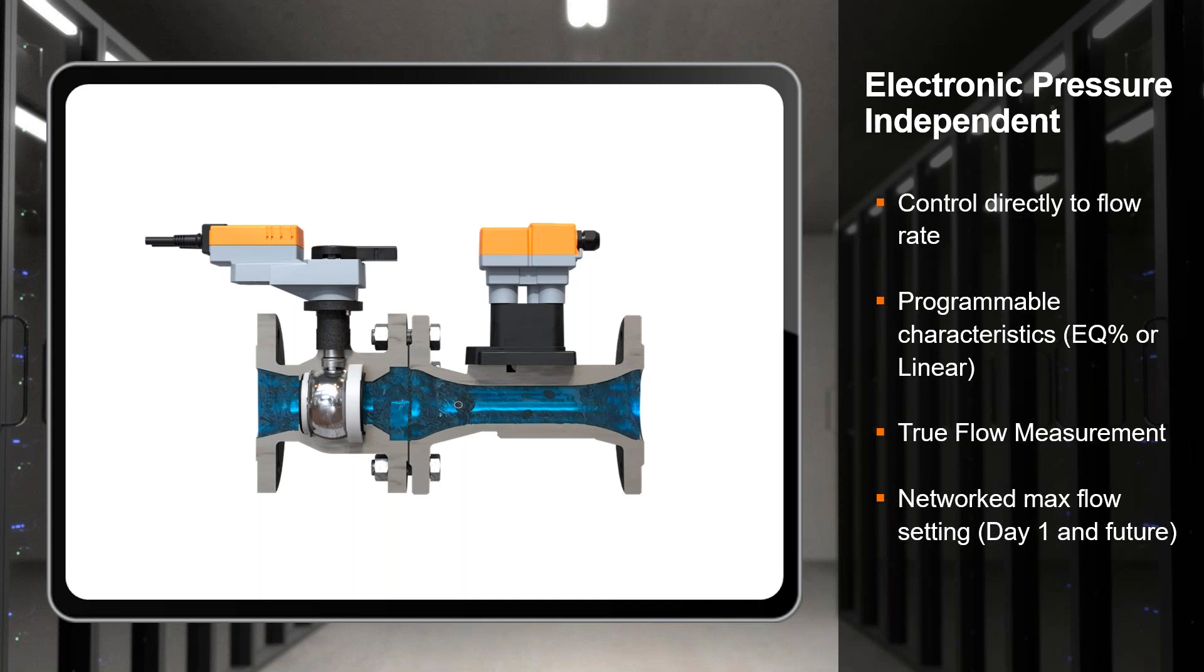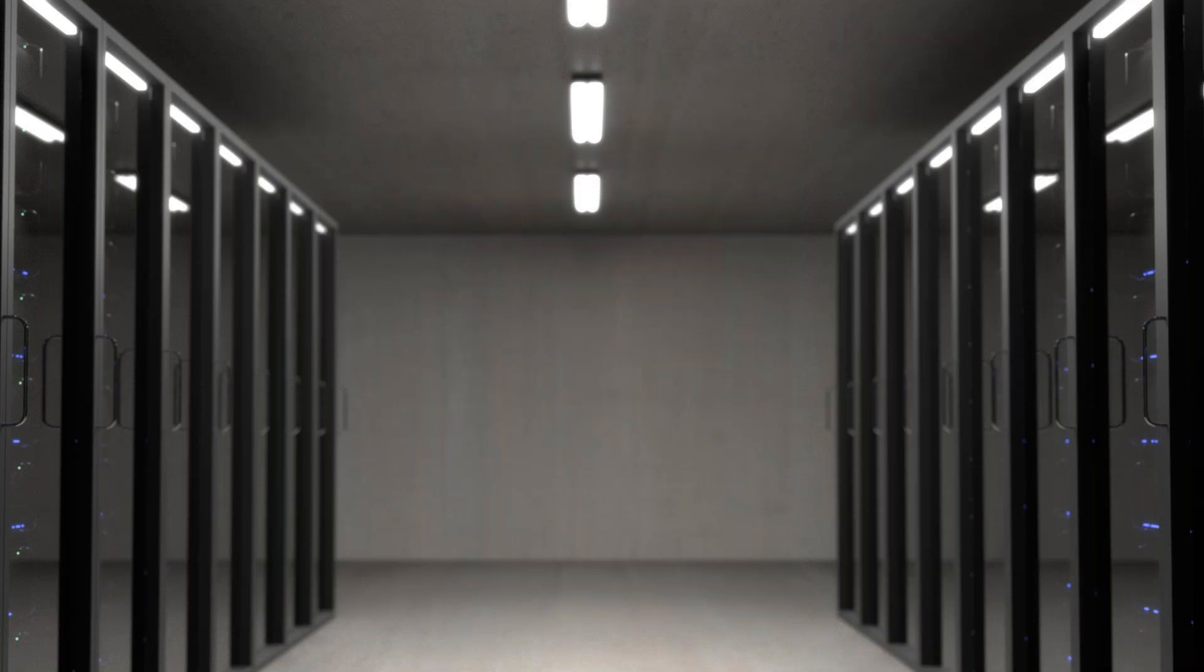The other option which really makes a big difference is the fact that these valves are available with BACnet and Modbus capability, which means I can network them completely. This allows me to reprogram the maximum flow rate of my valve. So today I need 10 gallons a minute to run my liquid cold plate racks, but two years from now I might need 12 or 14 gallons a minute. As long as we've selected a valve that has more capacity than we need today, it can simply be reprogrammed. If we compare the EPIV to a mechanical pressure independent valve, you can change the flow rates but it's a manual operation. You could use a flow setter valve which just limits the top end flow, but none of those devices will report the flow rate and none are remote reprogrammable. This gives us a huge advantage.